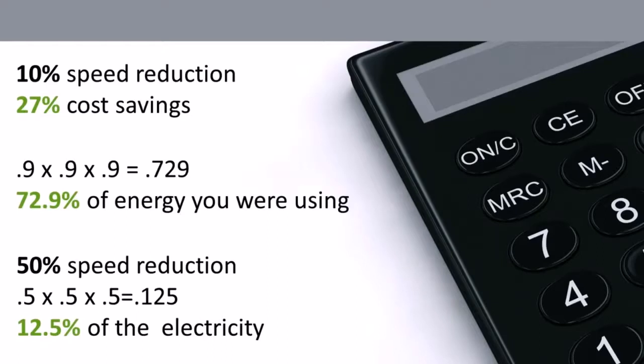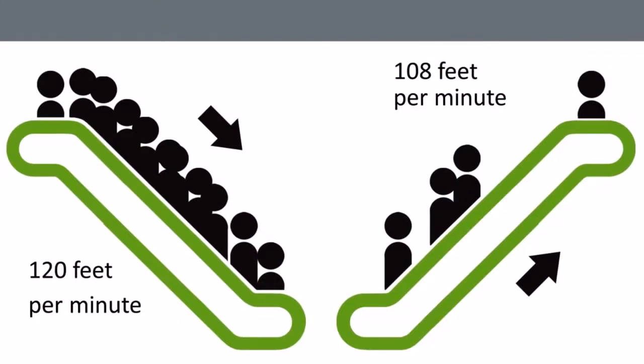What a variable frequency drive does is match the amount of energy your motor needs to the amount of work that's being done. This saves energy, a lot of energy. Think of an escalator. Let's say the motor is sized to carry a load of 50 people at its top speed of 120 feet per minute when there is a peak rush. But when there are only 4 people using the escalator, the motor is hardly loaded, and with a simple 10% reduction in speed that would be unnoticeable by the people, it would cut 27% of the energy consumed. Now that is what a VFD can do.